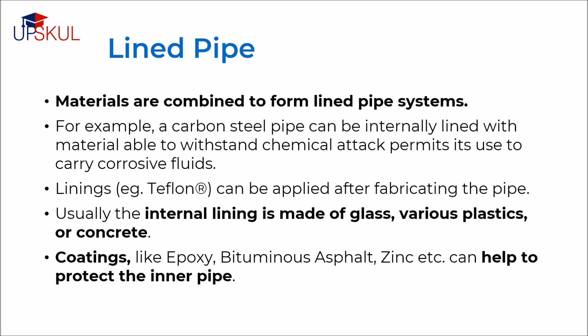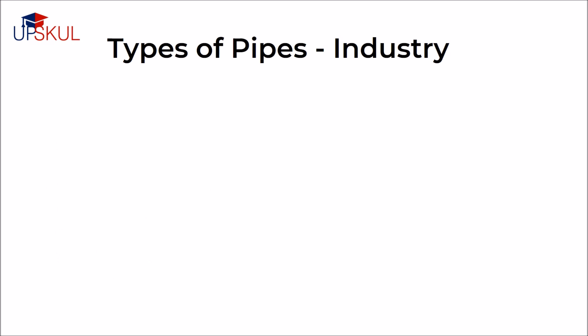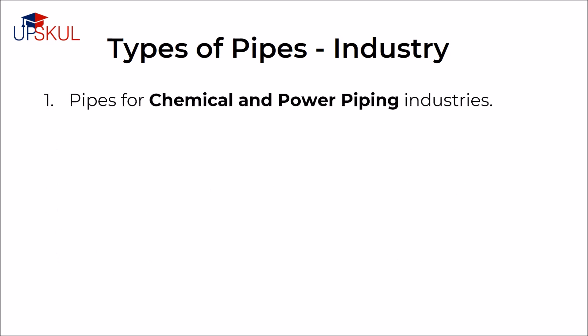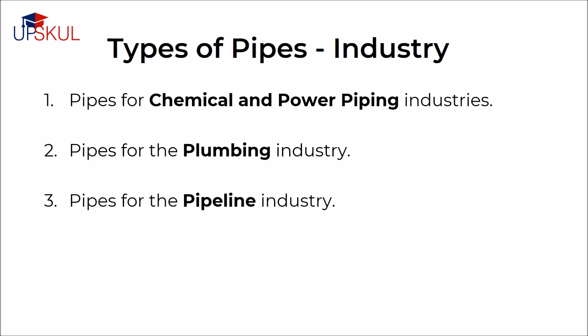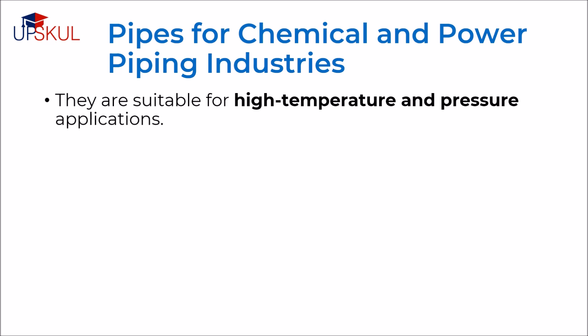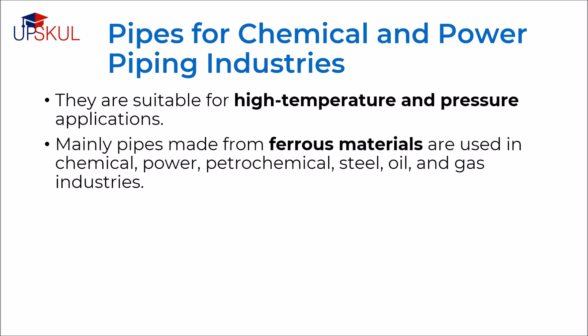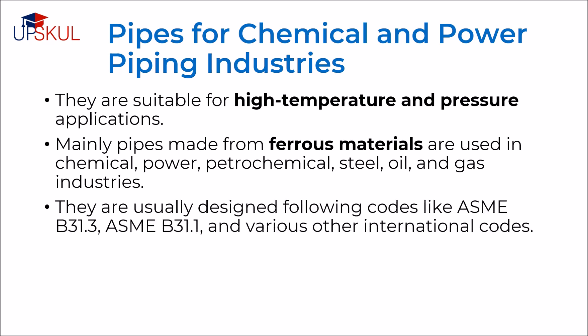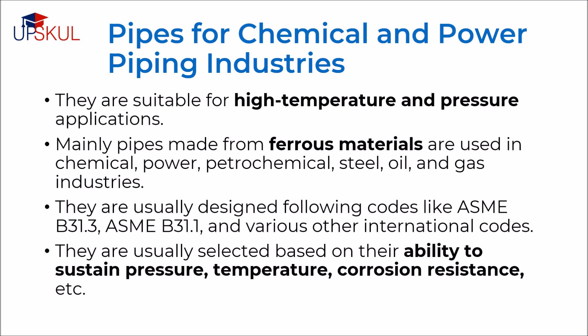Depending on the type of industry, there are three types of pipes: pipes for chemical and power piping industries, pipes for plumbing industries, and pipes for pipeline industries. The types of pipes for chemical and power piping industries are suitable for high temperature and pressure applications. Mainly pipes from ferrous metals are used in chemical, power, petrochemical, steel, oil and gas industries. They are usually designed following codes like ASME B31.3 and ASME B31.1 and various other international codes. They are usually selected based on their ability to sustain pressure, temperature, corrosion resistance, etc.